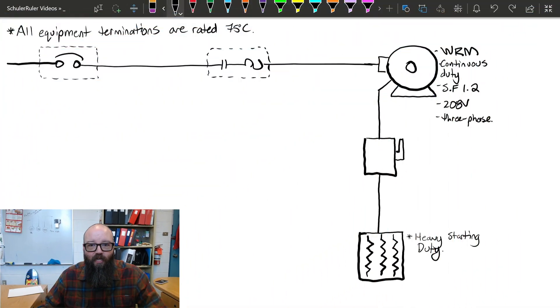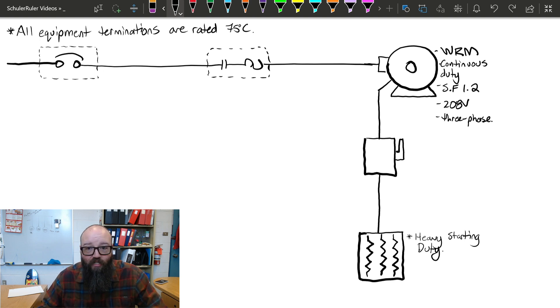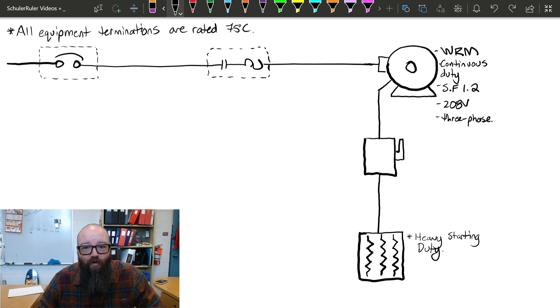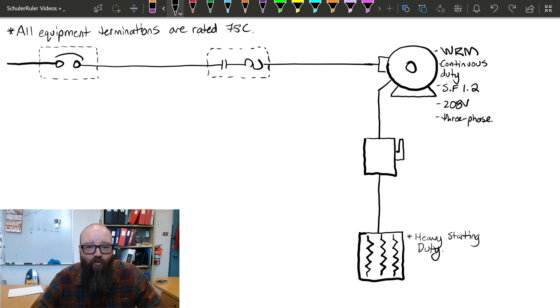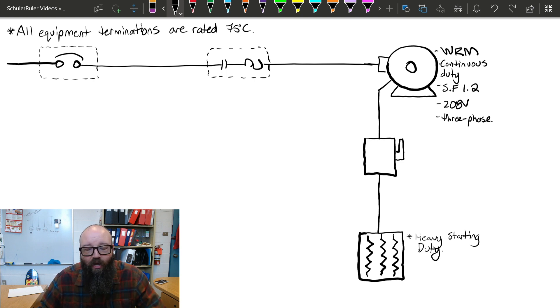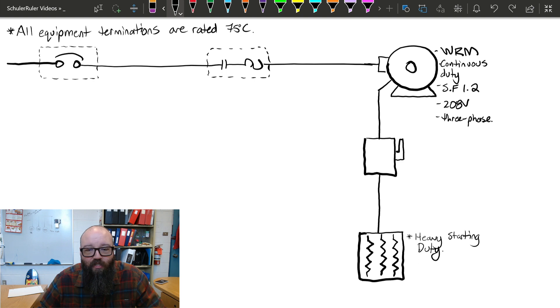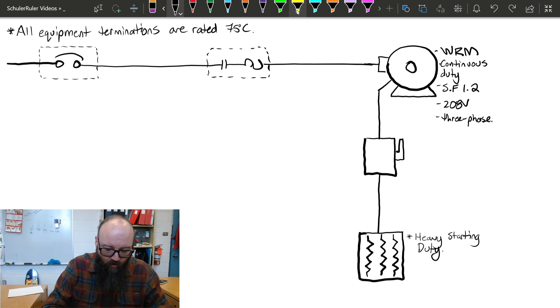We've got a little bit of information on the drawing here. We have the fact that it's continuous duty, we have a service factor of 1.2, 208 volts, three phase. All of these are factors we need to take into consideration when doing all of that standard stuff like branch circuit calculations, overcurrent calculations, and overloads. So to start off with our branch circuit calculations, it doesn't change from how we do a normal branch circuit calculation.